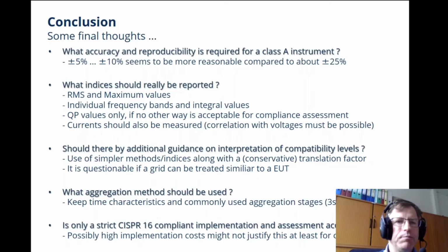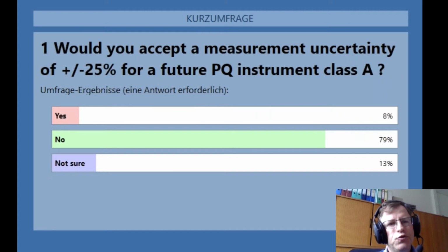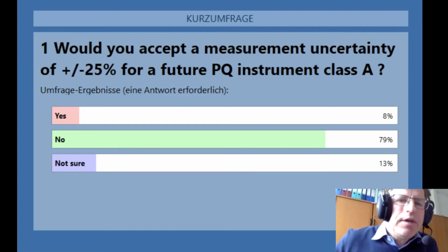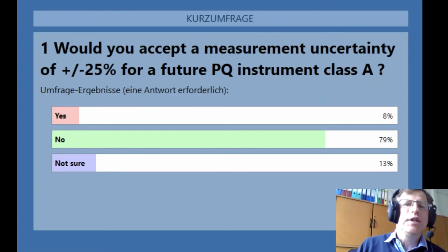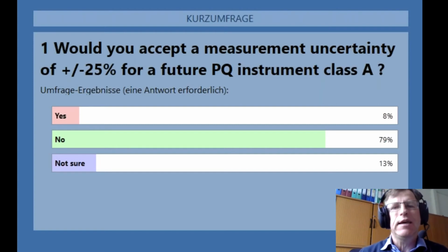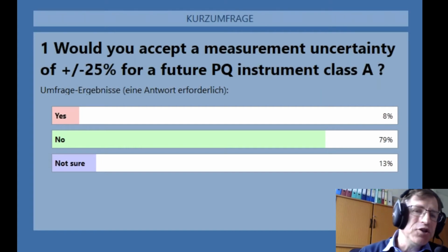And for sure, what about currents? Currents are quite important in my opinion, and that has also been shown by the 430 development, where in Edition 2 currents were introduced as informative, while in Edition 3 they became normative. So why not already consider currents? But CISPR 16 doesn't deal with currents at all. So what should we maybe require from working group 8, to give additional guidance on how the compatibility levels that they have defined in 61000-2-2 have to be interpreted with regard to grid measurements? What aggregation methods?